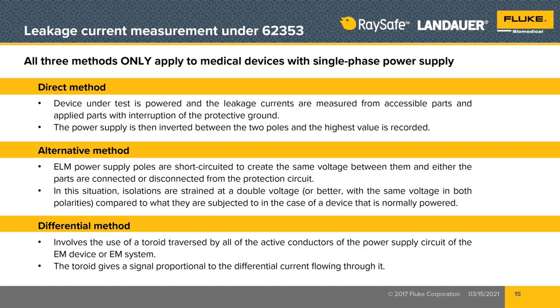So we will be doing single fault testing along with the rest of the tests that we will do under the direct method. The power supply is then inverted, meaning we reverse the polarity, and that means we would say to ourselves, what happens if L1 and L2 are connected backwards? They are not connected where they're supposed to be. They've somehow been cross-connected. We will reverse the polarity, therefore, and we will do the testing again in reverse polarity. So that's what happens in the direct method.